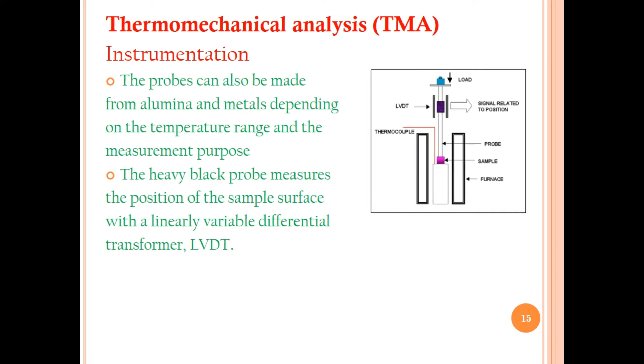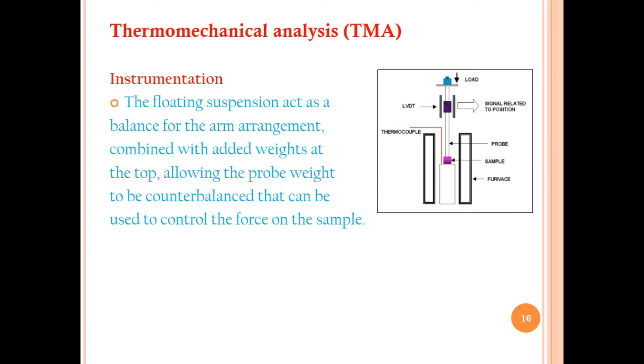The heavy black probe measures the position of the sample surface with the linear variable differential transformer, LVDT. Again, LVDT is a sensor for measuring expansion and contraction in the sample behavior after applying force by a load in the TMA technique. Instrumentation continues. The floating suspension acts as a balance for the arm arrangement combined with added weights at the top, allowing the probe weight to be counterbalanced, which can be used to control the force on the sample. So this is the load applied on the sample by a probe. The LVDT sensor detects the compression or the contraction when load is applied on the sample in the TMA technique.